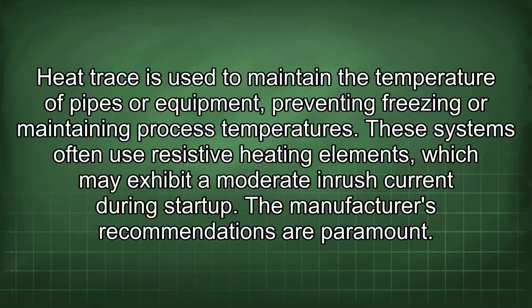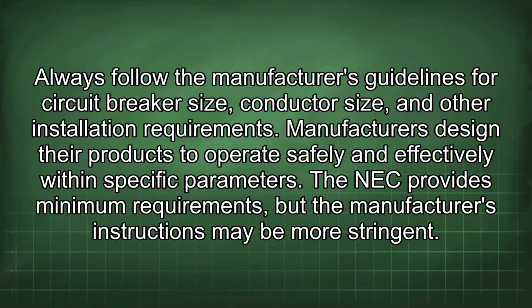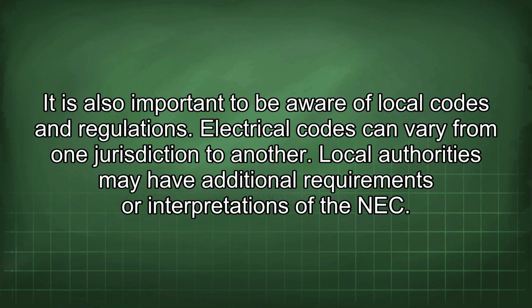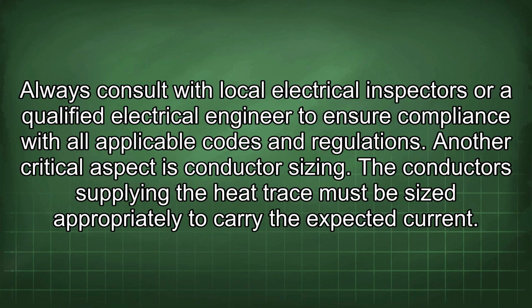The manufacturer's recommendations are paramount. Always follow the manufacturer's guidelines for circuit breaker size, conductor size, and other installation requirements. Manufacturers design their products to operate safely and effectively within specific parameters. The NEC provides minimum requirements, but the manufacturer's instructions may be more stringent. It is also important to be aware of local codes and regulations. Electrical codes can vary from one jurisdiction to another. Local authorities may have additional requirements or interpretations of the NEC. Always consult with local electrical inspectors or a qualified electrical engineer to ensure compliance with all applicable codes and regulations.